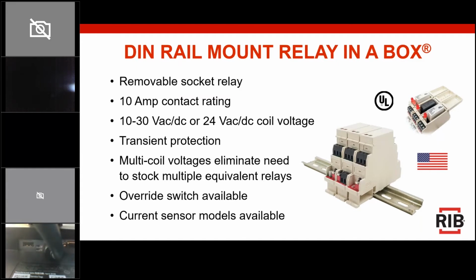If you look at the top right there, you're going to see that it's a removable socket relay. Once it's wired to the panel, if you need to replace a relay, you can just pop that out, put the new relay in, and you're ready to go. And then on that bottom picture there, you can see the lids on the relays. There's two indicators there. One of those will be for the relay, and if you do the current sensor built-in, there's an LED located on top for that as well.